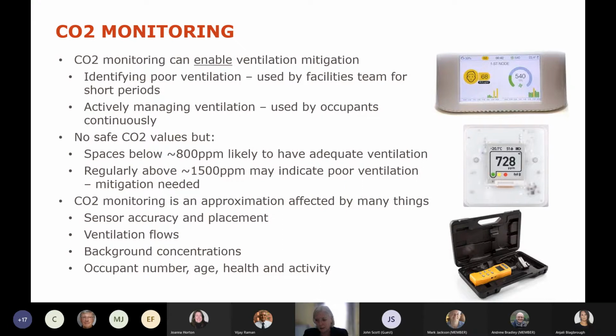So, to open windows or change ventilation settings in response to a CO2 concentration, there's no safe value. We can't put a single number on it, but looking at the balance of data out there, spaces below 800 parts per million normally probably have adequate ventilation. If spaces are routinely above 1500 parts per million, there's a chance it's poorly ventilated and you need to do something about it. If it spikes above for a few minutes, that's really not a problem. It's when it's there routinely and sitting above those values that matters.